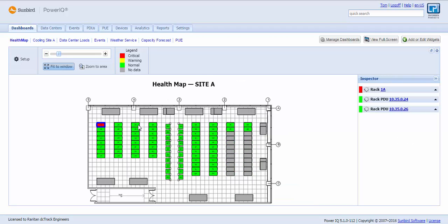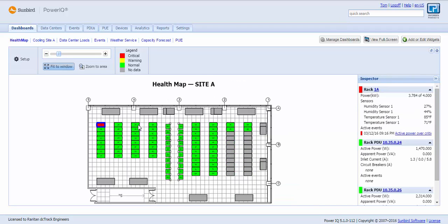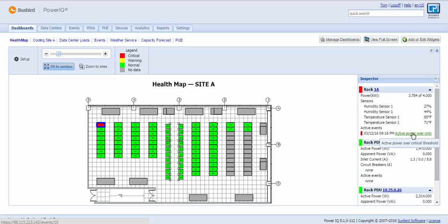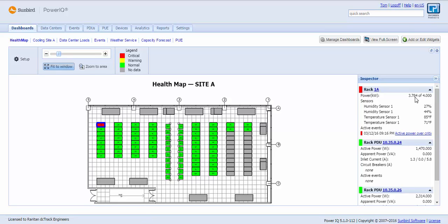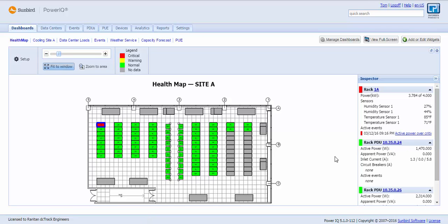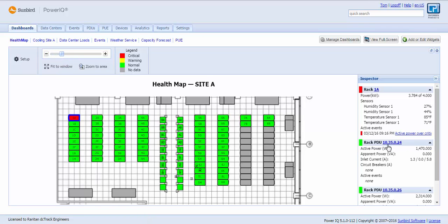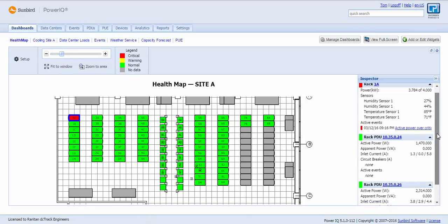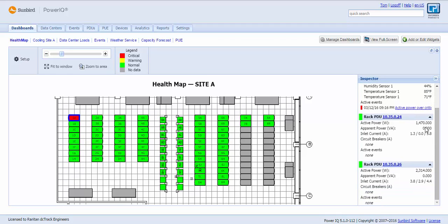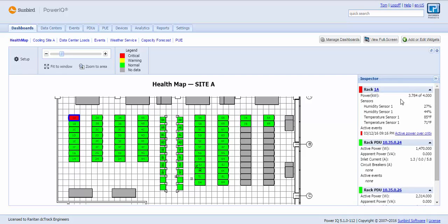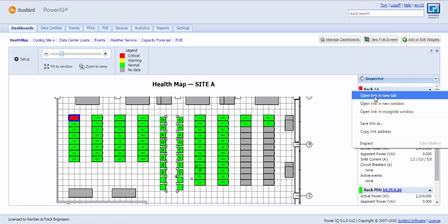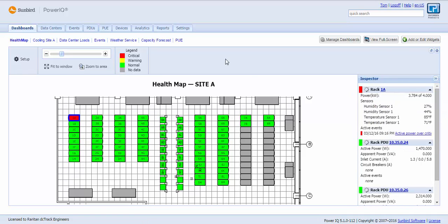I click and I can drill down and open up an inspector and get the cabinet load, the cabinet capacity, sensor conditions, and the alerts that have caused this cabinet to go into a critical condition. In this particular case, we're measuring the load of the cabinet and comparing it to thresholds that were set by the user on the capacity of the cabinet, and that is what has been violated. I can also look at the individual rack PDUs, their load, their inlet currents, and if there are any conditions that are triggering warning or critical alerts. I have hyperlinks to further drill down, so if I want to drill down into 1A, I might open that up into a new tab.